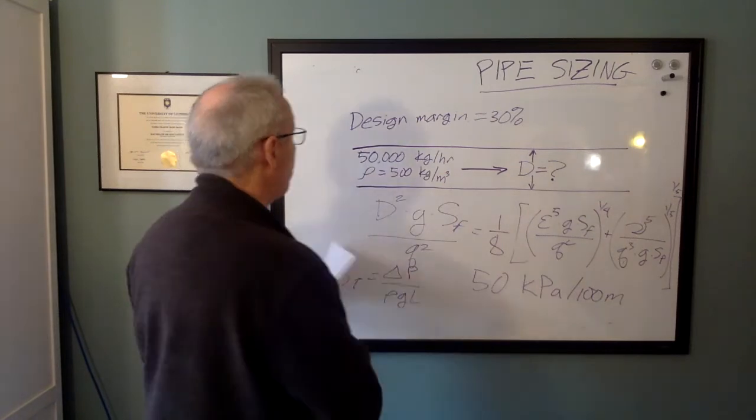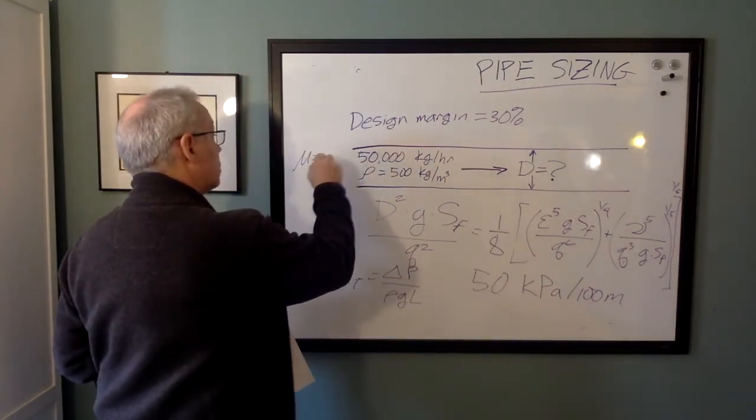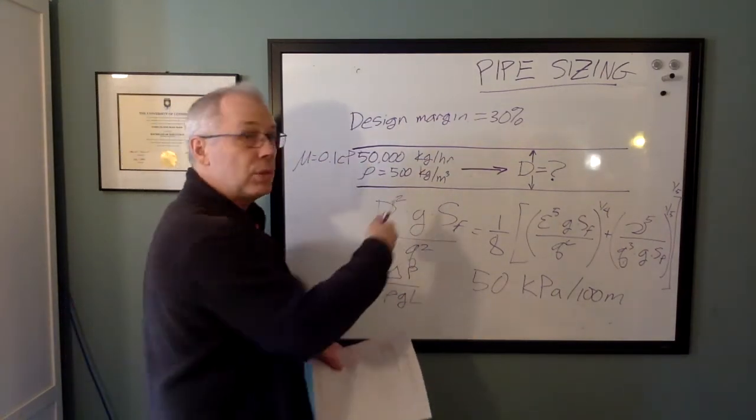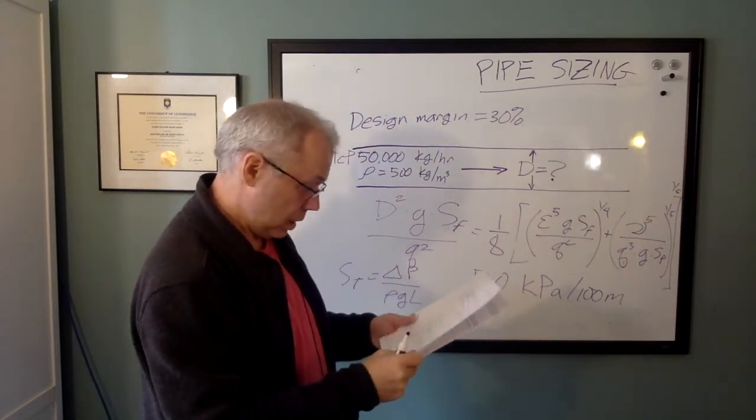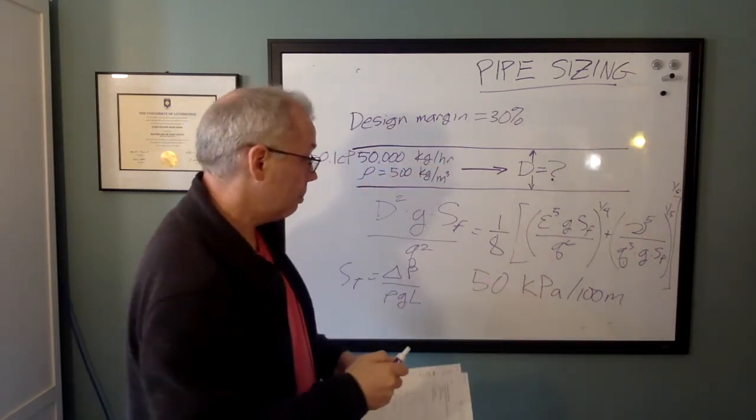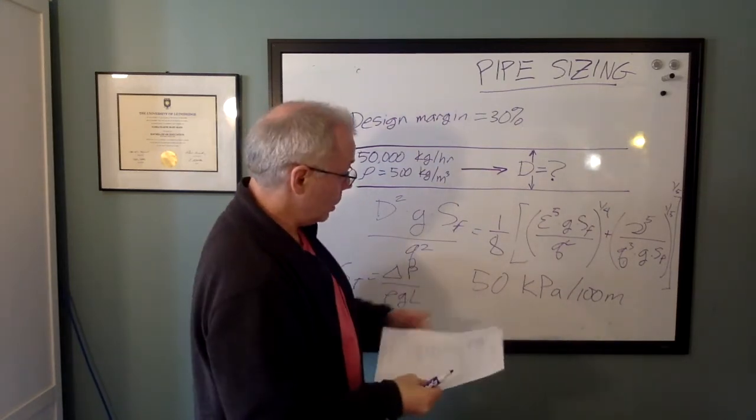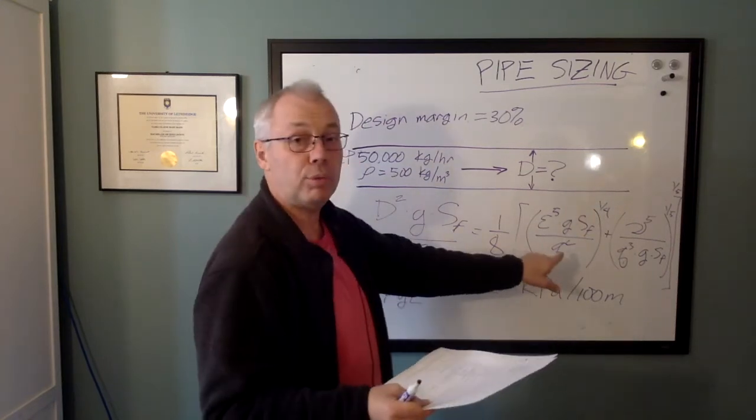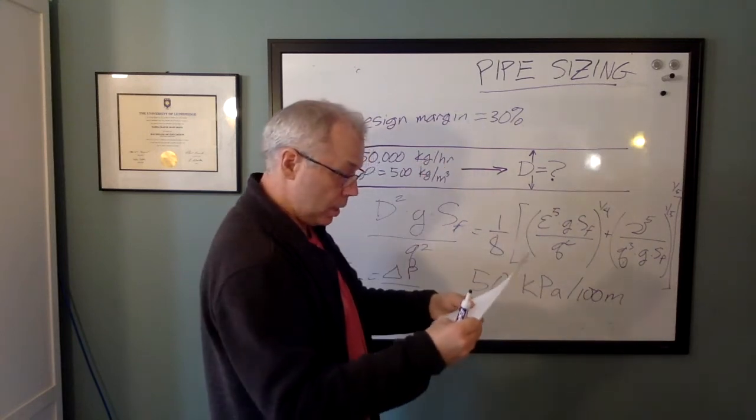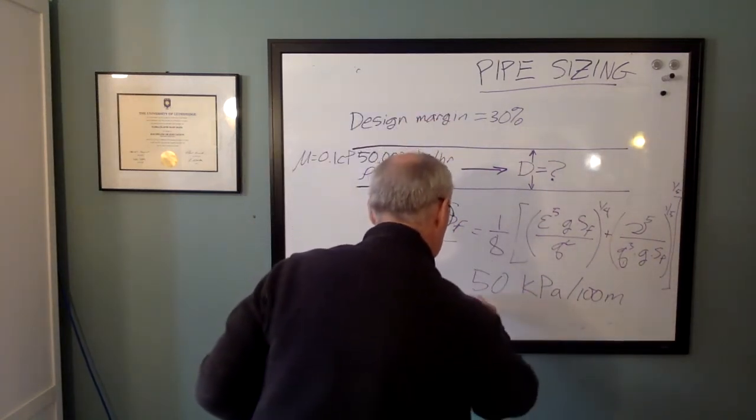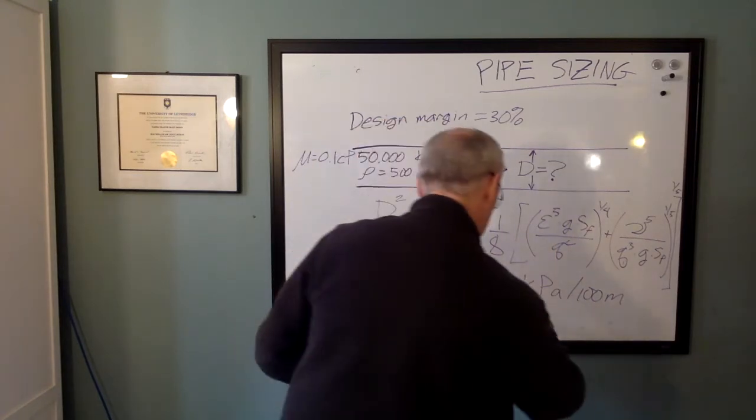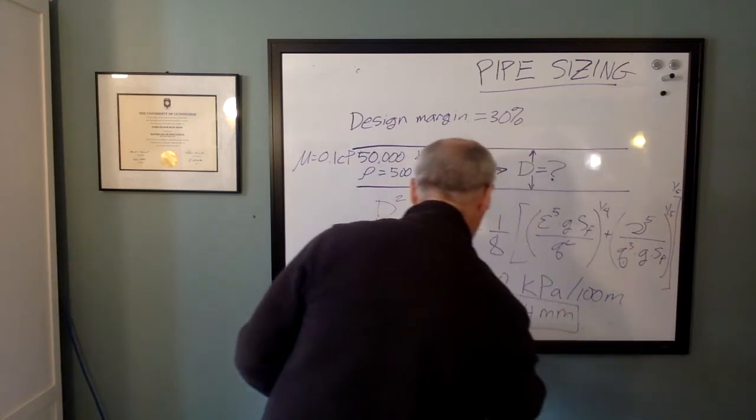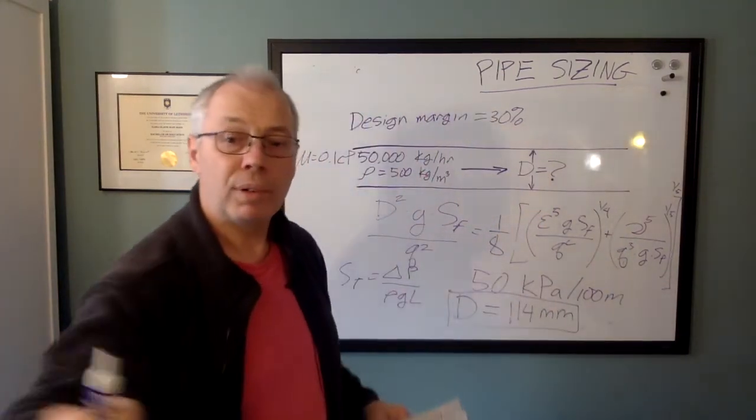Our fluid liquid propane has a viscosity of 0.1 centipoise, so we divide that by the density and we can get the kinematic viscosity. And now we can just crunch through the math. And what we get using this criteria, 50 kPa per 100 meters and that nasty formula, is in one shot we can calculate that we need a pipe diameter of 114 millimeters.